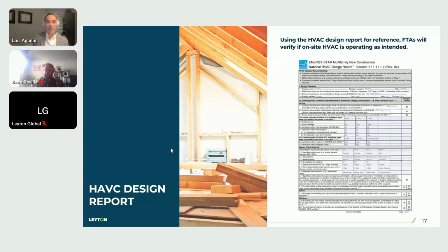So here's an example of the HVAC design report itself. Here's just the first page and what it looks like. It's a multiple page document that we take a look at. Some of the things on this page are the loads for the rooms, the sensible load for each room, the latent load for each room, and the specifications for the AC unit itself.